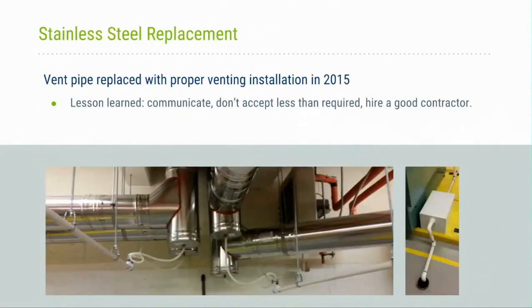Okay. About a year and a half ago, I did a project that went back into that room, and we redid the ductwork properly. As you can see from the other picture, there was no drainage at the bottom of the duct. There wasn't anything saying, hey, we're going to have water condensing coming back from this flue. So all this ductwork has rubber gaskets in it, so when it snaps together, it's all sealed. And then, of course, the sealing of the ductwork on the outside, too. So it is a specialized ductwork that's called out for in code and in the installation manuals.